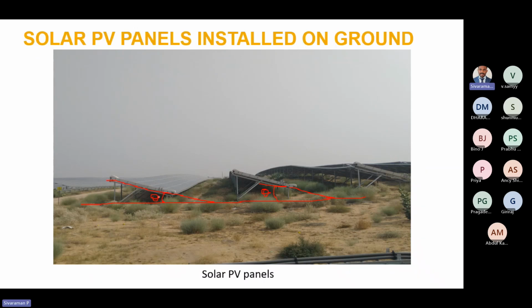Here the PV panels will be connected in series as well as parallel, based on the requirement, to make the stringing, right? The stringing is applicable for string inverter. Similarly, we have to perform the stringing for central inverter as well, to match the nameplate detail of the central inverter.